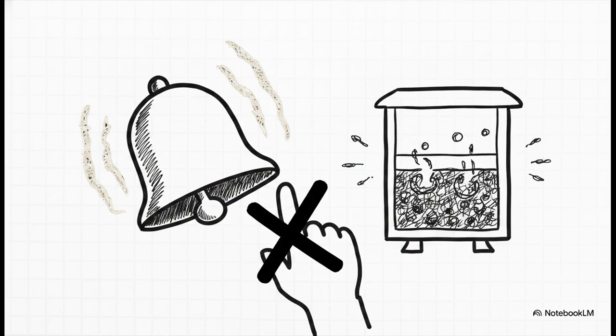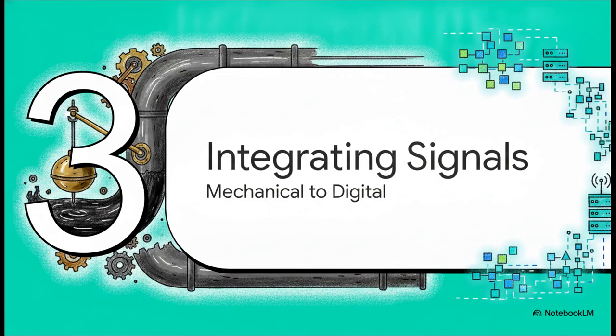And here is a crucial, absolutely crucial warning. Never, ever treat a stage 1 Buchholz alarm as a nuisance. Don't just silence it until it's convenient to go check. Remember that timeline. If you're getting a Buchholz alarm, your transformer oil is actively decomposing right now. It is very often the earliest available warning of a dying asset, showing up way before the electrical protection even knows anything is wrong.